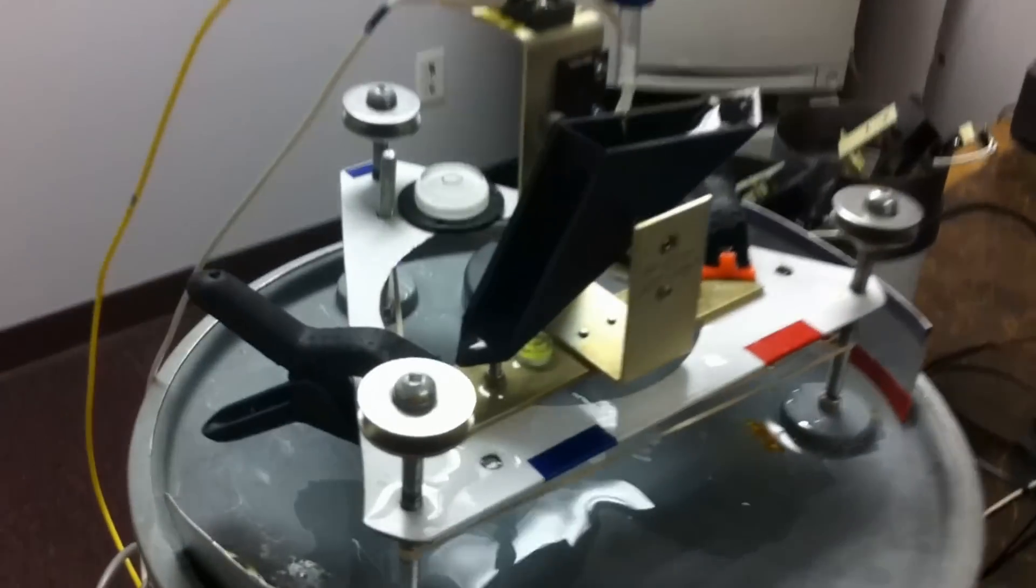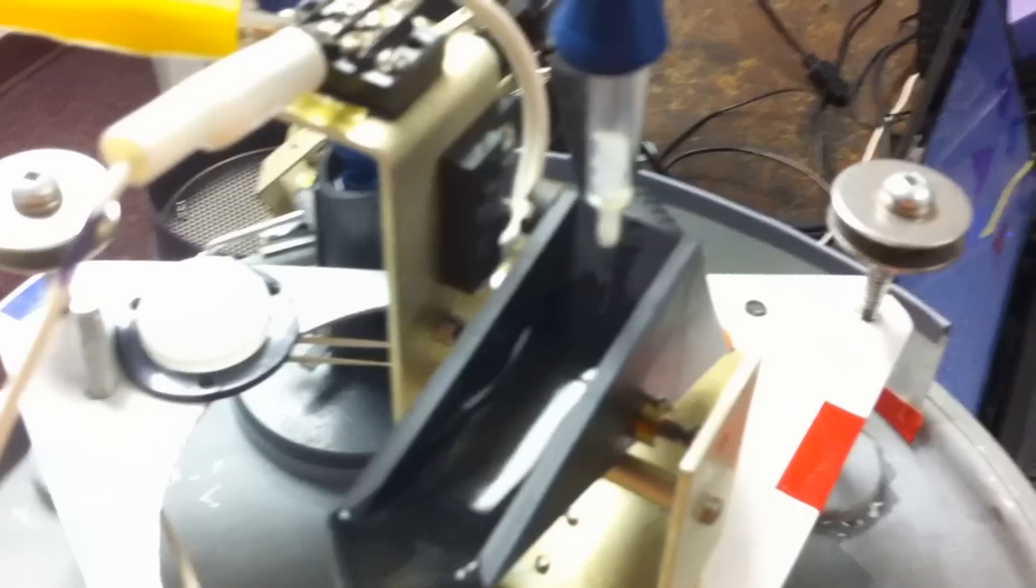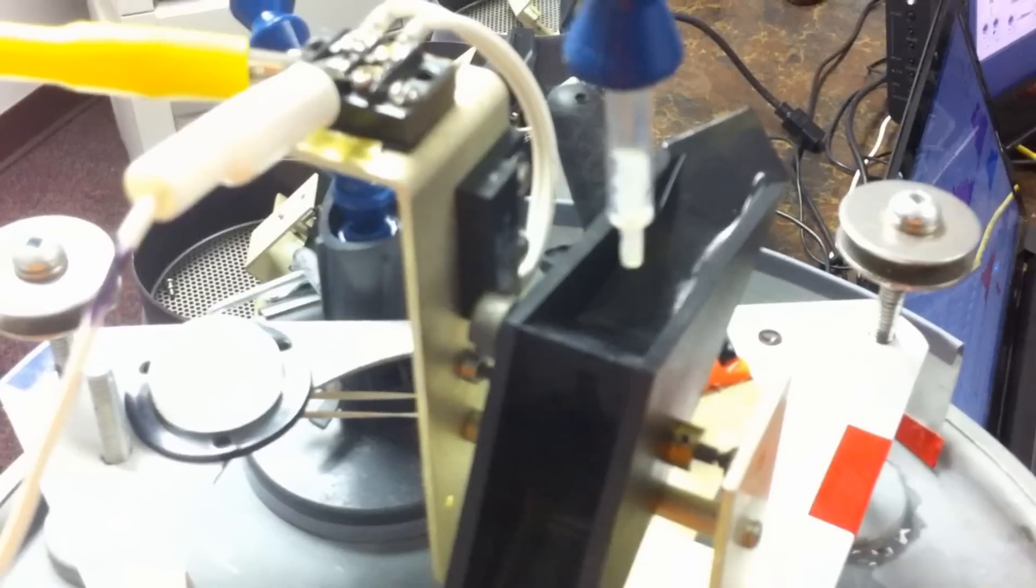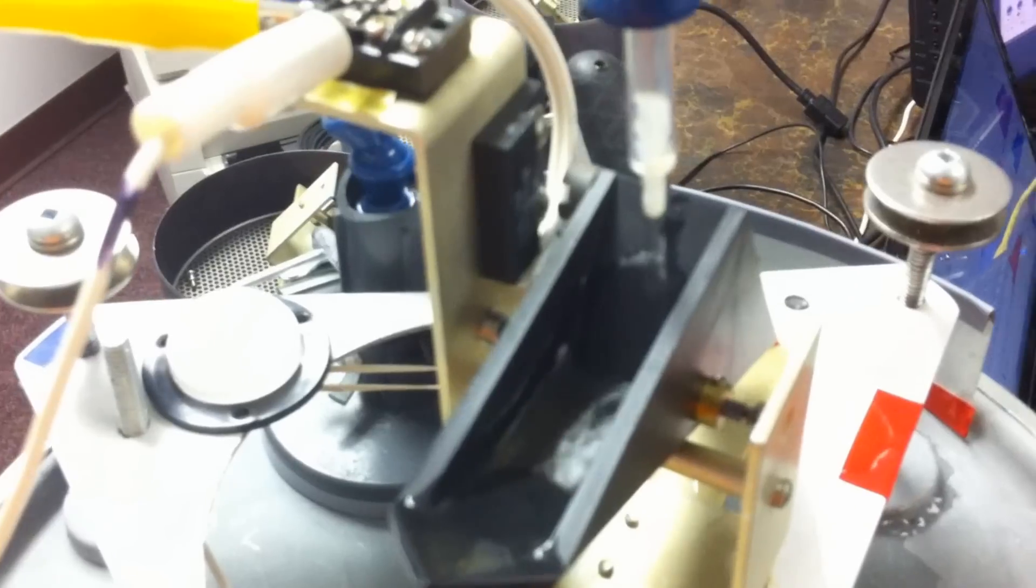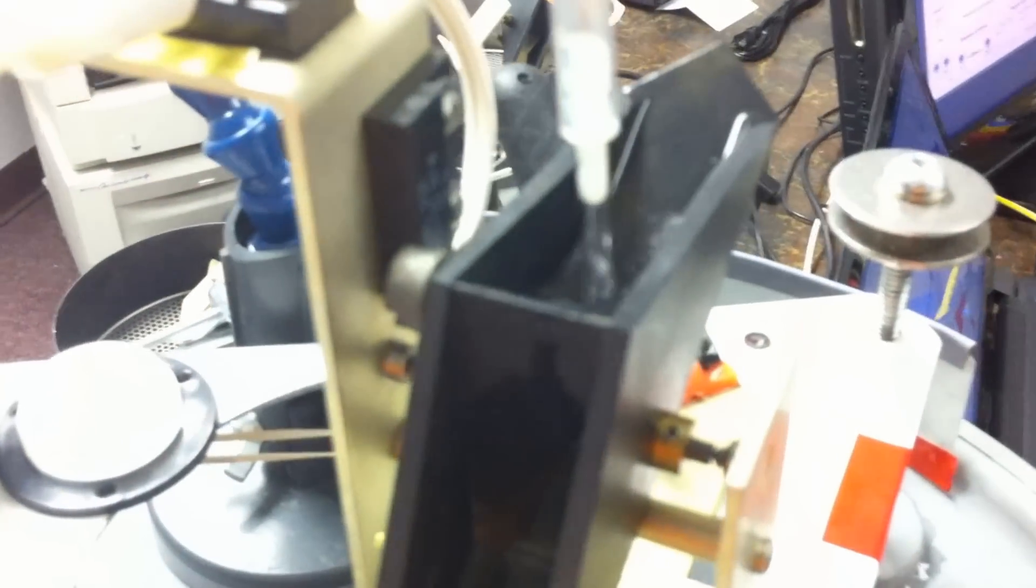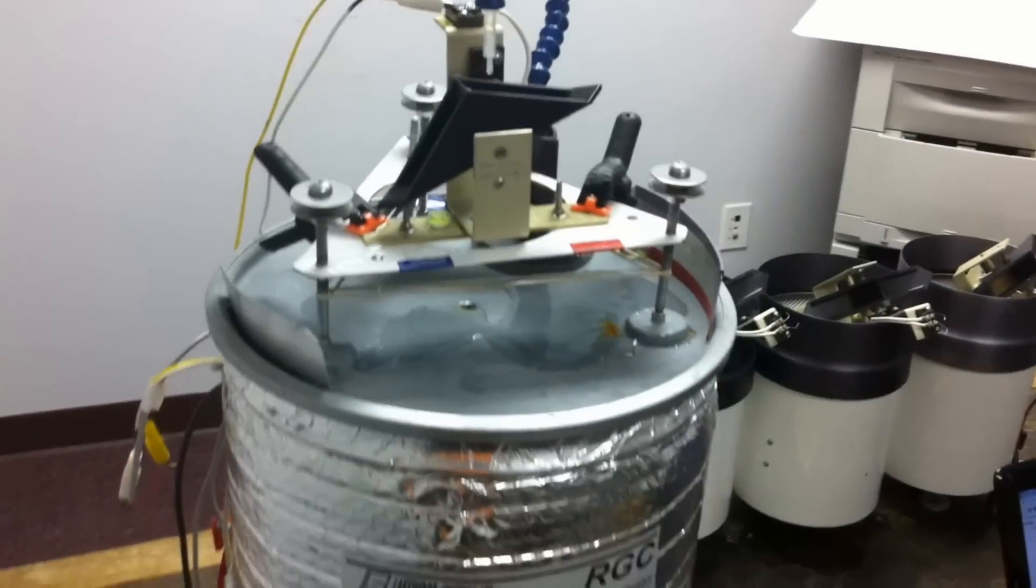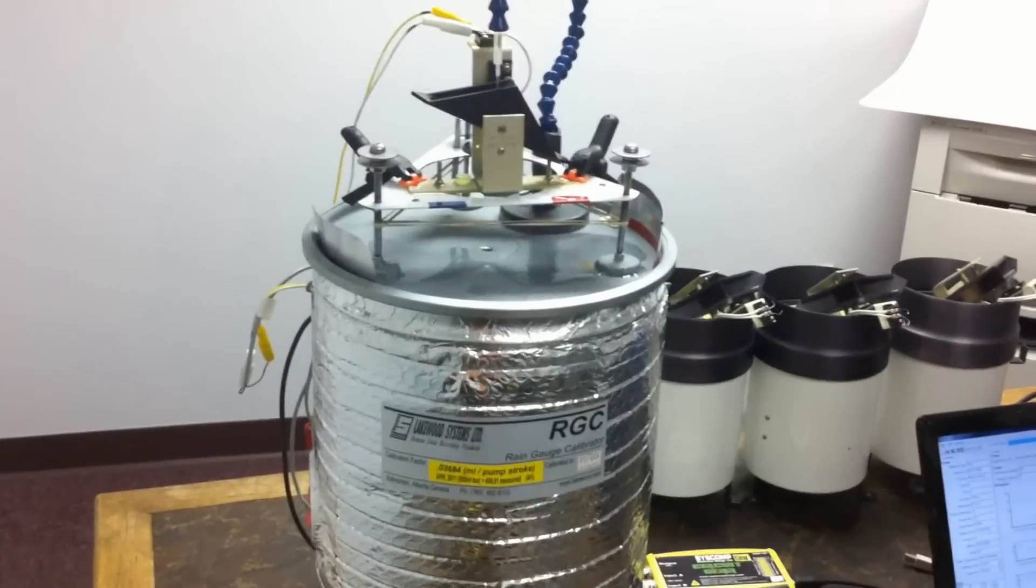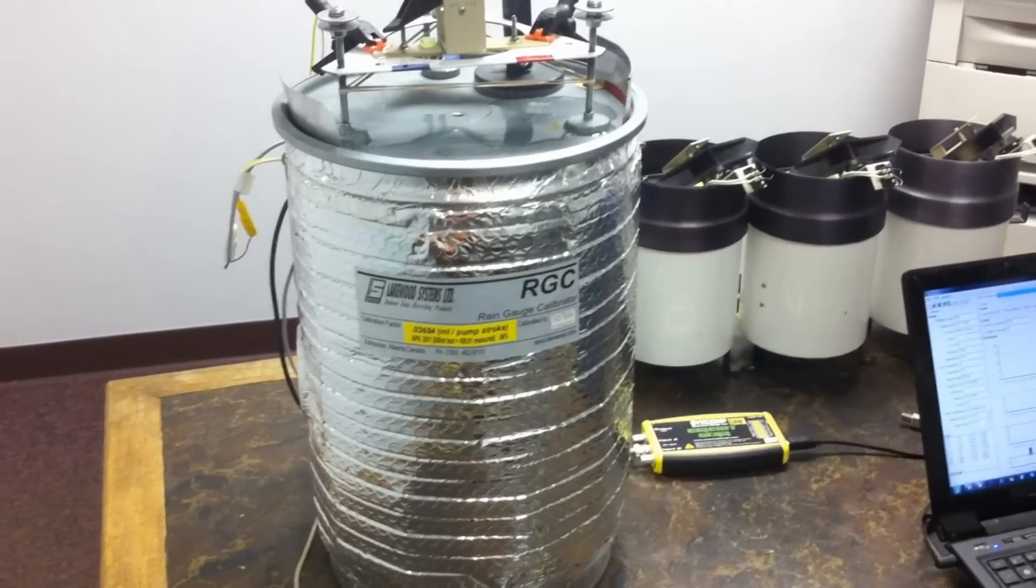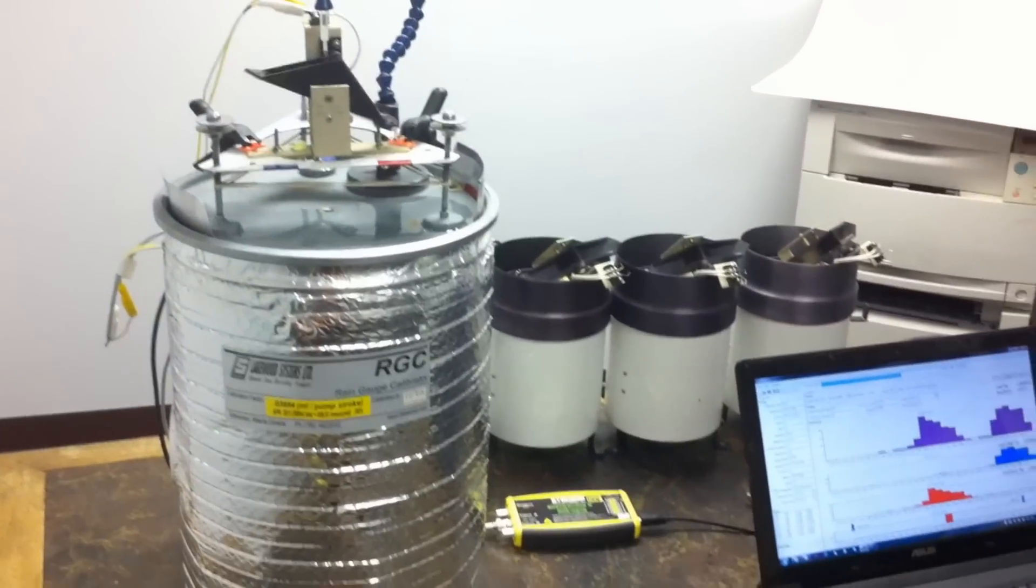We take a look at the operation of the rain gauge calibrator here. We can see that a variable speed pump is putting water into each side of the tipping bucket through this tube. We also notice that the bucket fills quite quickly initially and then the pump backs off. We can see the individual pump strokes here as it does the final fill just before the tip. This rain gauge calibrator is all battery operated, so this whole process can be performed in the field. The unit will do about 15 to 20 calibrations between battery charges.